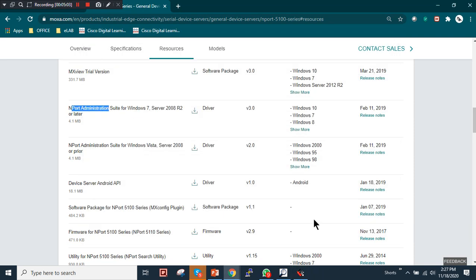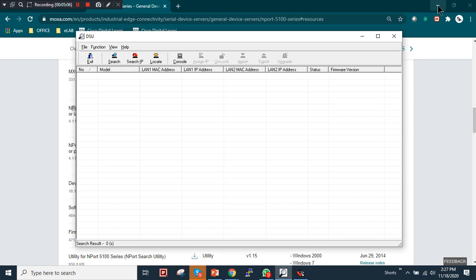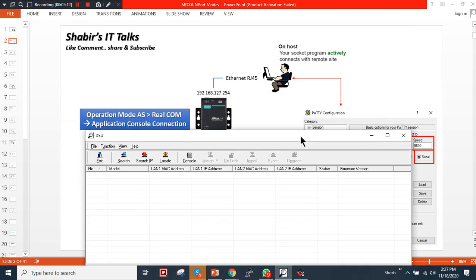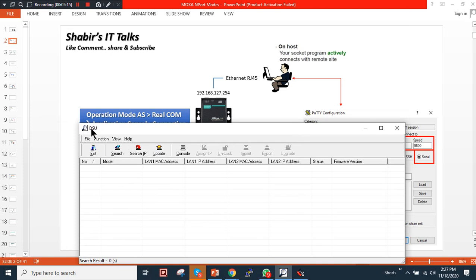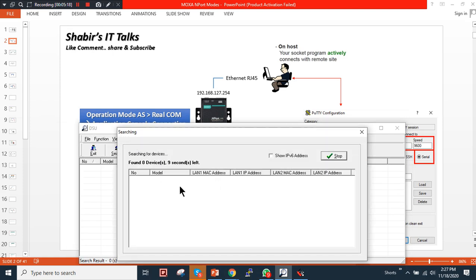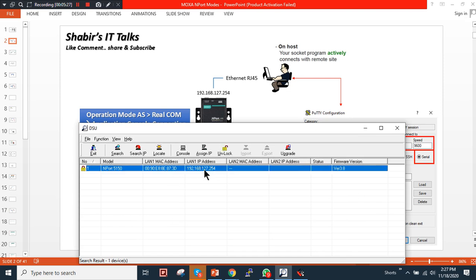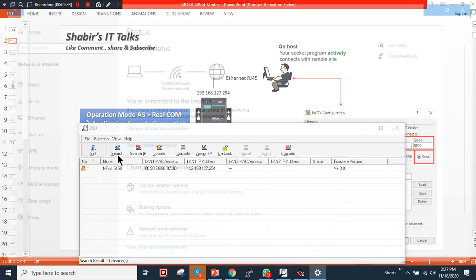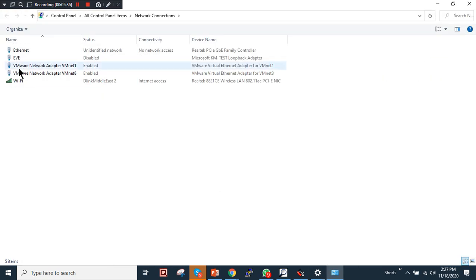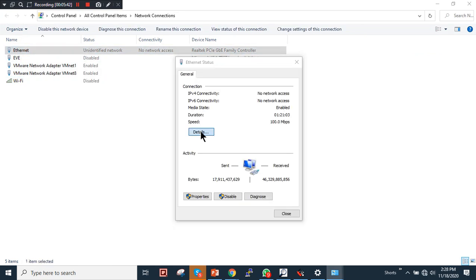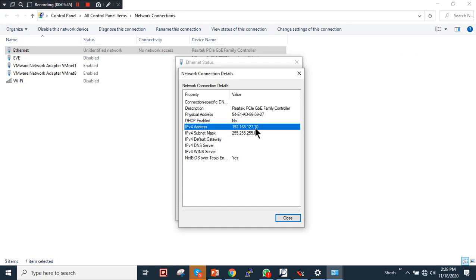When you first connect your cable to the device and don't know its IP address, use the DSU utility. Install it on your PC, run a search, and as you can see the NPort 5150 is discovered. The IP address of the serial converter is 192.168.127.254. I need to assign my PC an IP address in the same subnet — I already have 192.168.127.70 assigned.